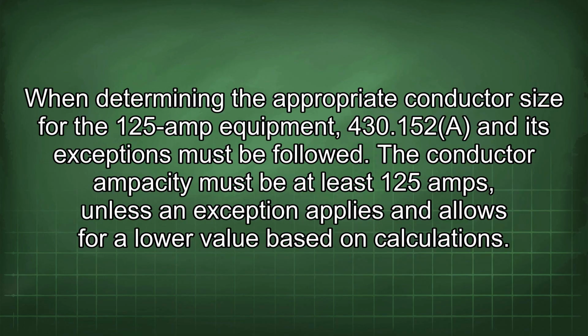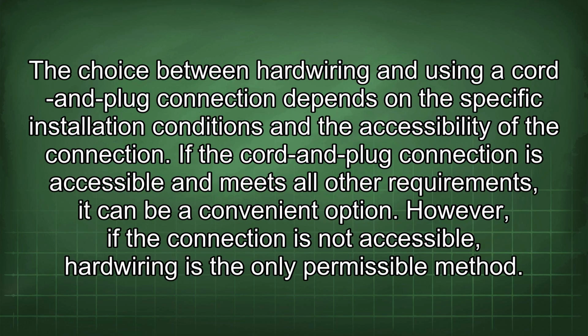When determining the appropriate conductor size for the 125 amp equipment, 430.152 and its exceptions must be followed. The conductor ampacity must be at least 125 amps, unless an exception applies and allows for a lower value based on calculations. The choice between hardwiring and using a cord and plug connection depends on the specific installation conditions and the accessibility of the connection. If the cord and plug connection is accessible and meets all other requirements, it can be a convenient option. However, if the connection is not accessible, hardwiring is the only permissible method.